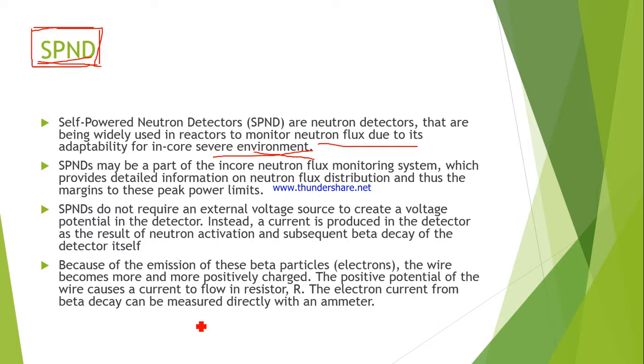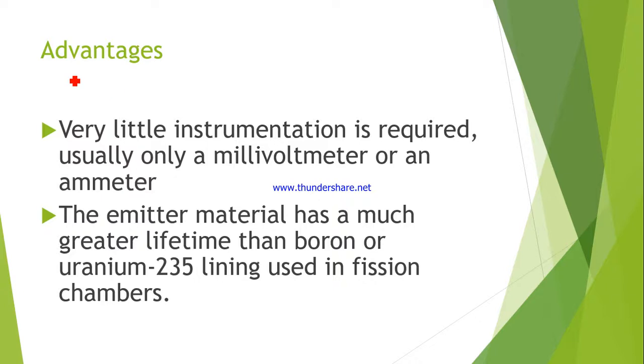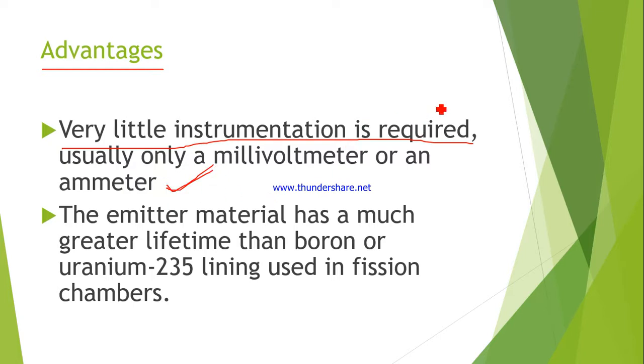Since no external voltage source is needed, this is called a passive device. The electrode itself — the emitter — emits beta particles, which are electrons. The electrons flow through the external circuit and can be easily measured by a conventional current measuring device without complicated electronics. Very little instrumentation is required; usually only a millivoltmeter or an ammeter is sufficient to measure the current, which is then mapped to the desired physical quantity.